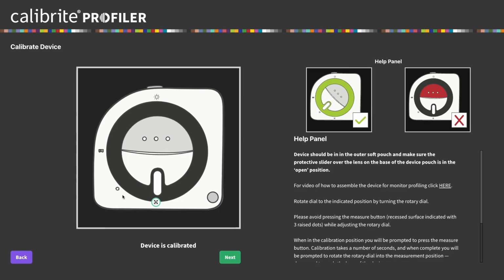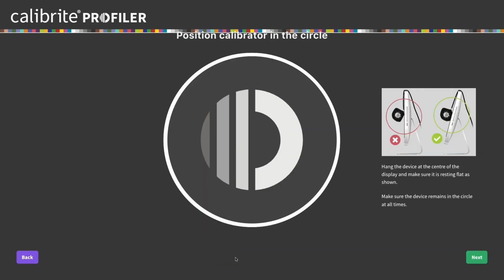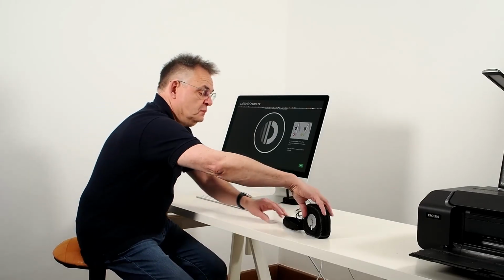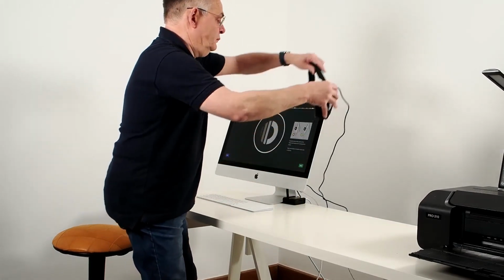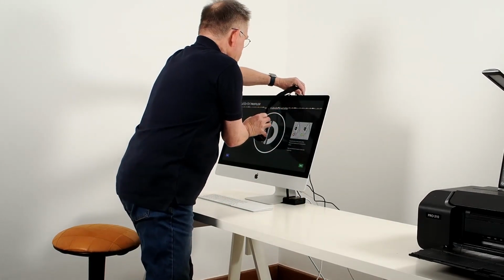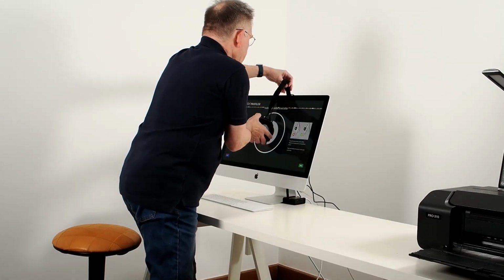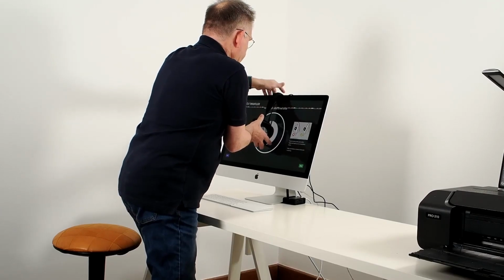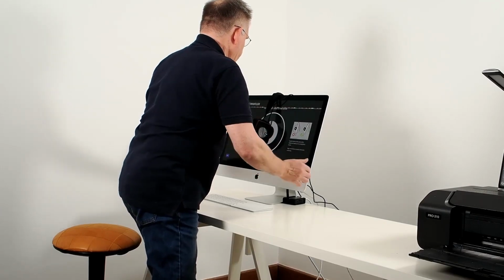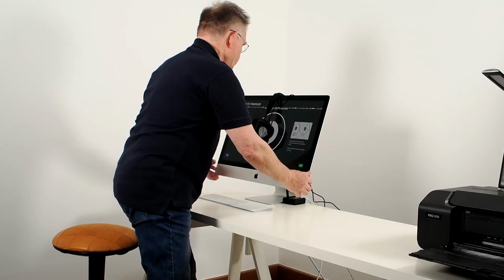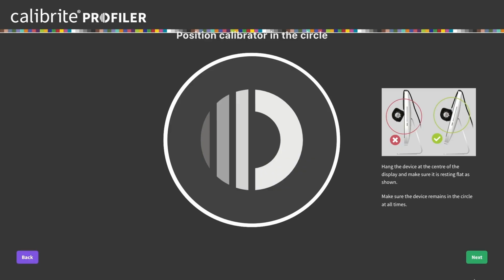Once that's been rotated, we get the message that the device is calibrated and we can now use it to measure the screen. So we press next, and this is where we have to hang the device at the center of the display. Now we're using the lead-weighted strap to counterbalance, and we're going to actually tilt the screen backwards a little bit. We can then press next again.